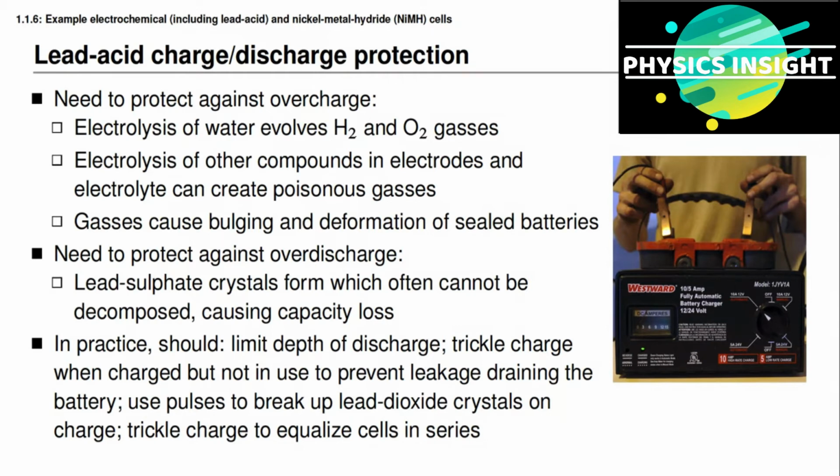And you're going to find out next week, when we look at lithium-ion battery cells, that we cannot do trickle charging with lithium-ion battery cells because they are too efficient and they will just keep on charging forever and ever until they catch fire and explode. And of course, we have to avoid that. So the trickle charging in a lead-acid cell allows cells that are already fully charged to remain in that state, while the remaining cells in the battery continue to charge until all cells are fully charged.